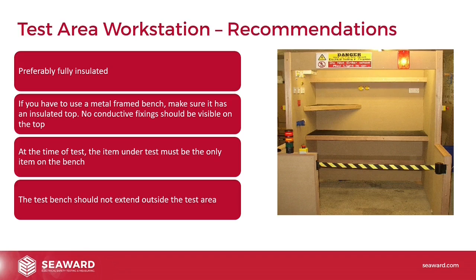So you don't want that wood being screwed down with bolts into a metal table and those bolts visible on the top, because they are, of course, providing a path to ground into the metal chassis or the metal frame and then down to ground. At the time of test, we only want one item on the bench at any time. The theory being that if you have a bench full of things you are testing or about to test, and one of them becomes live, it could cause a chain reaction where something it's touching becomes live, the next thing becomes live, potentially leading to a situation where something is live that you wouldn't expect it to be. The test bench should also not extend outside the test area for the same reason.